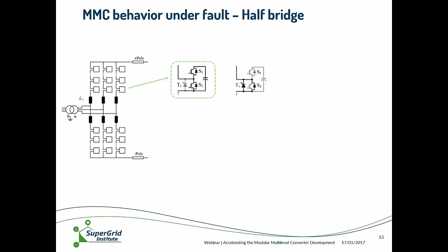The MMC will stop the discharge of the capacitor into the fault by blocking the IGBTs, and then will auto-protect its IGBTs, more precisely its freewheeling diodes, by switching on a parallel thyristor which will bypass the submodules. Finally, the entire converter will behave like a diode bridge.